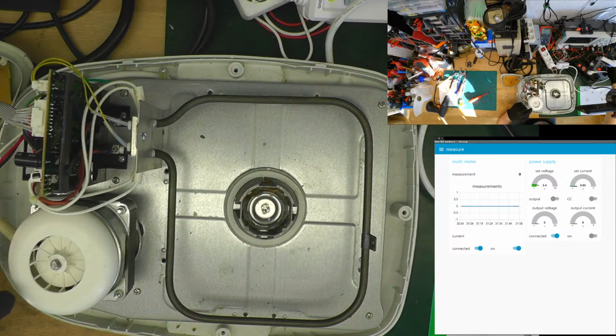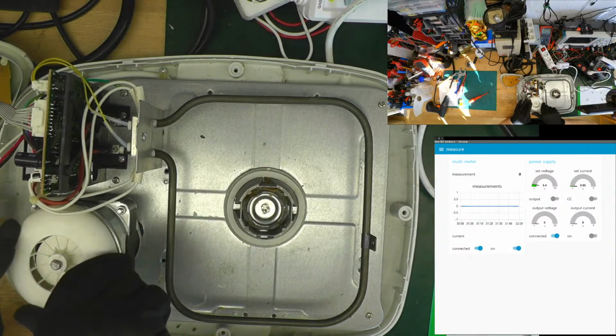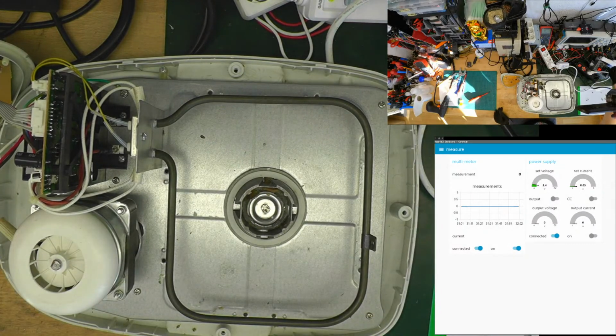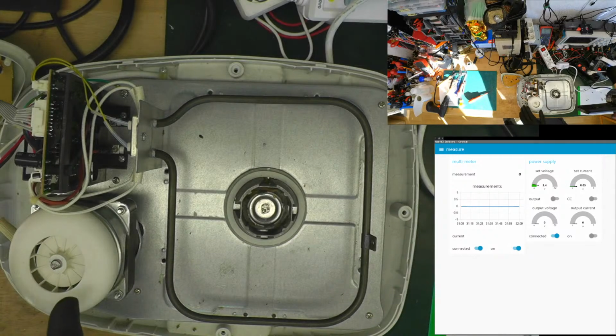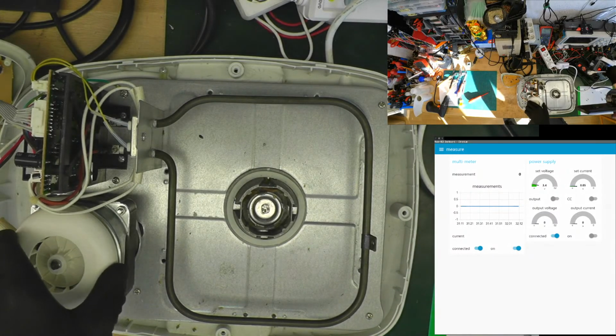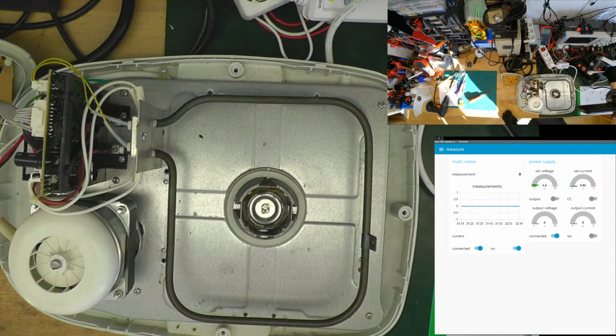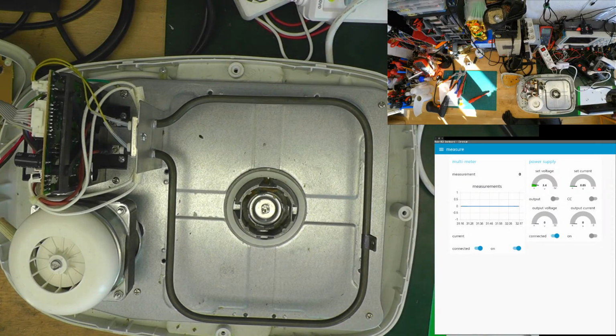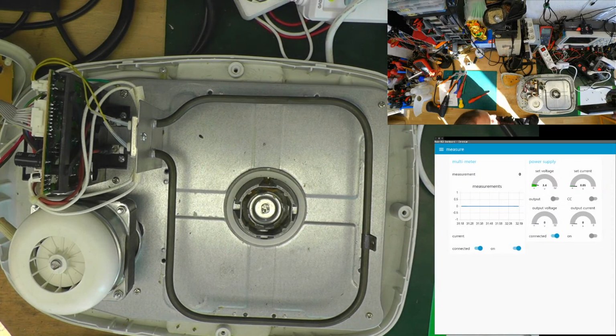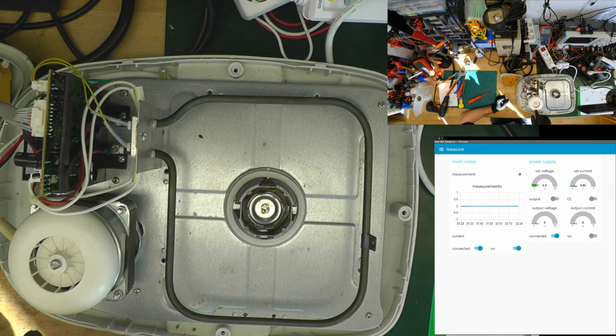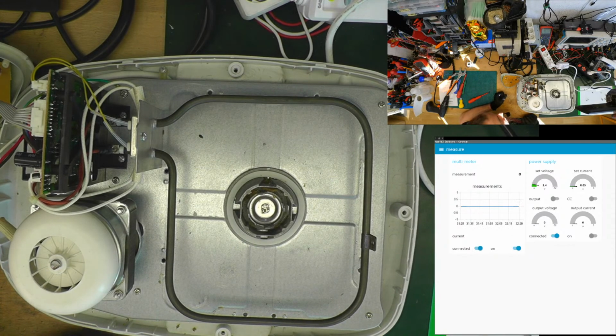There's one of the coils which is broken. This is why it can't continue, it's working partially. When I turn it a bit here and switch it on, it turns a bit, and then it stops. I think one of the windings is broken, and this is why it can't turn anymore, so I can't use the motor. Probably this is where there was an earth connection, and it tripped when the motor was braking, turning down. That would be my guess.